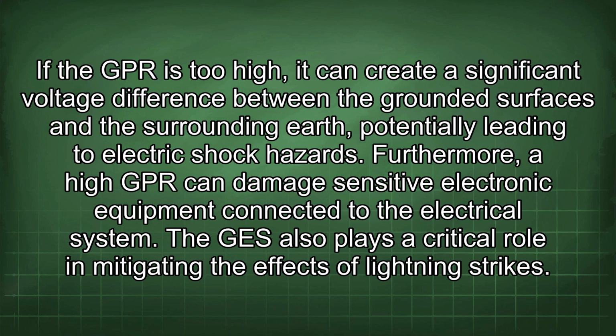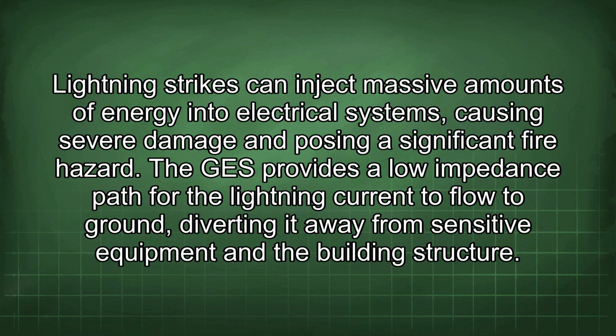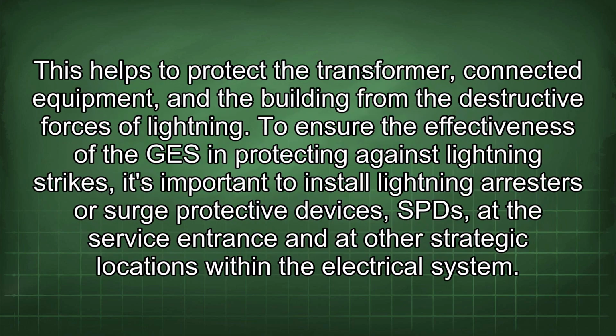The GES also plays a critical role in mitigating the effects of lightning strikes. Lightning strikes can inject massive amounts of energy into electrical systems, causing severe damage and posing a significant fire hazard. The GES provides a low impedance path for the lightning current to flow to ground, diverting it away from sensitive equipment and the building structure. This helps to protect the transformer, connected equipment, and the building from the destructive forces of lightning.